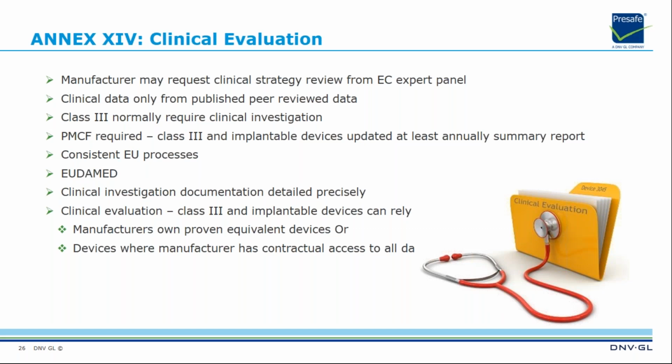This may require manufacturers to obtain additional clinical data from clinical studies. There will be additional scrutiny of clinical evaluation reports by notified bodies as outlined by new guidance, and clinical evaluation reports that previously were of a suitable level and standard and accepted by notified body may no longer be accepted.